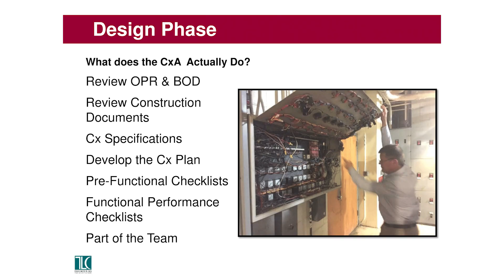Just like on HVAC commissioning, sequences of operation are very important to us. But unlike HVAC, and you might complain that the sequences you see aren't great, at least you get sequences of operation on your drawings or in your specs. If I'm reviewing a set of documents for emergency systems, I can almost write the first comment without even opening the set or the specs: provide a detailed sequence of operations and provide the time delay settings for the transfer switches, because nobody ever seems to bother to put that in the document. So that's a constant fight.